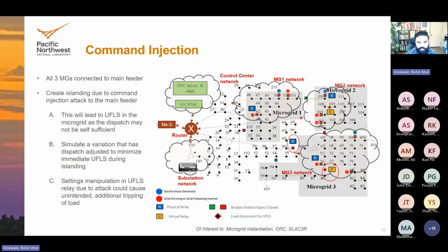So to give you an example, I'll show a scenario where that blue box is an SEL 351 relay. In this case, if we were to island the system by attacking that relay to open the breaker, microgrid 2 and 3 in this diagram would basically be islanded after that. That would be a forced islanding scenario, unplanned, where you aren't able to adjust system outputs to make it a smooth transition.